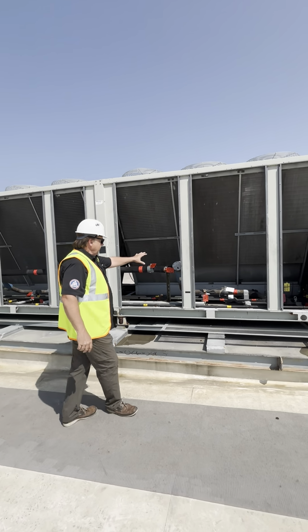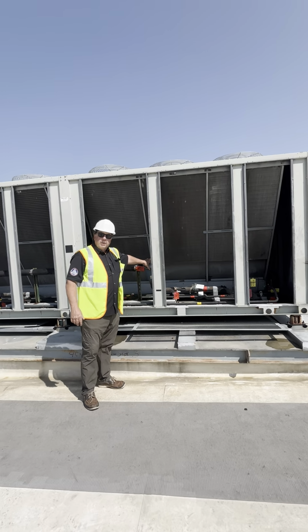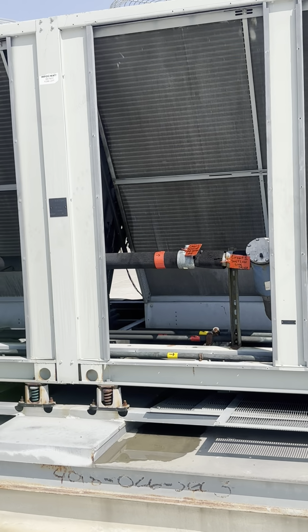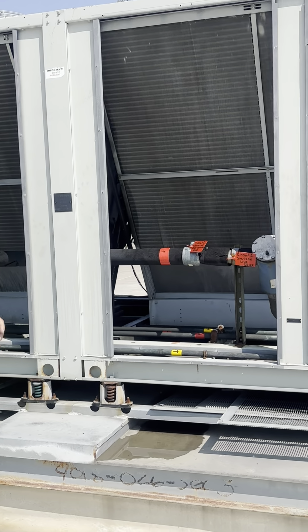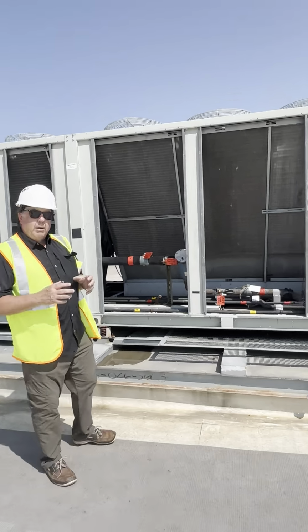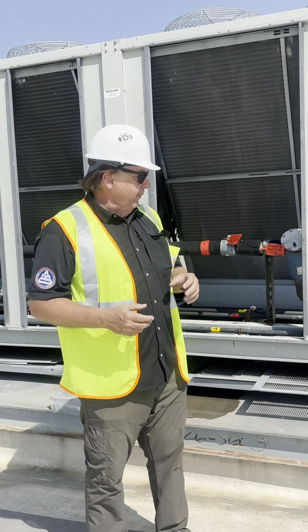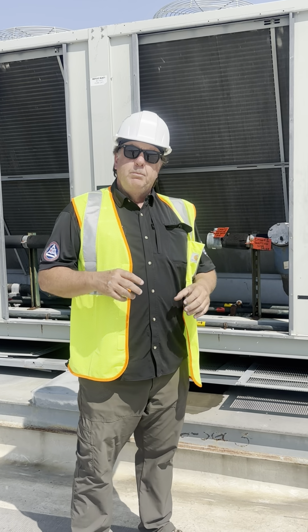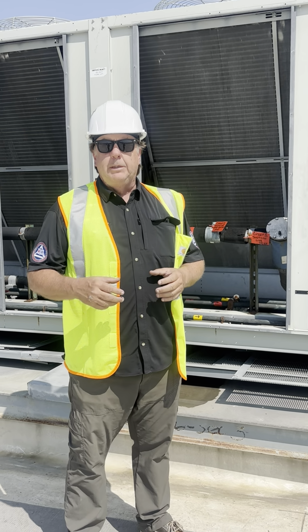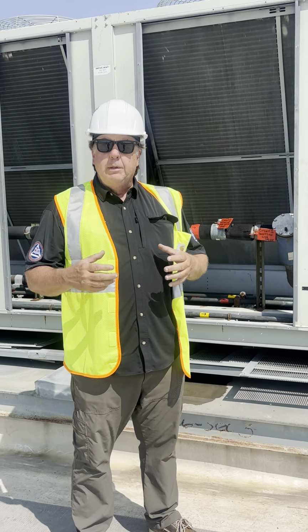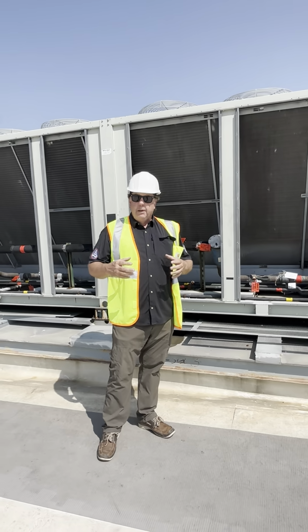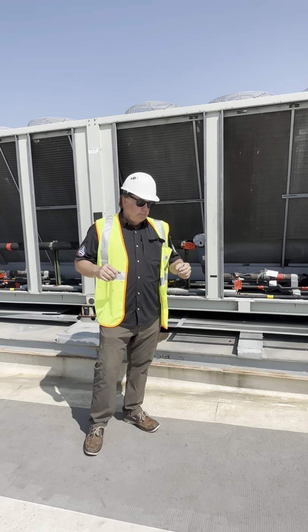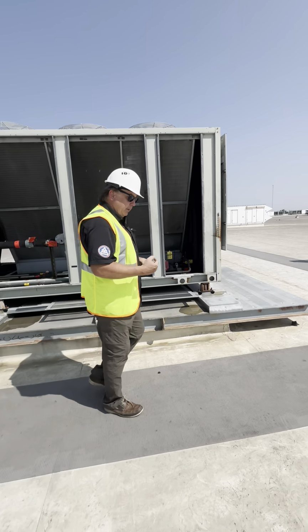We've got suction line filter dryers. On the room over here, we'll see we've got liquid line filter dryers. These units also have what they call hot gas bypass. They've got a myriad of cutouts, pressure reliefs, and check valves, and all these other things that have been added into it for this particular application. Just walk around the side, I'll show you the compressor side.